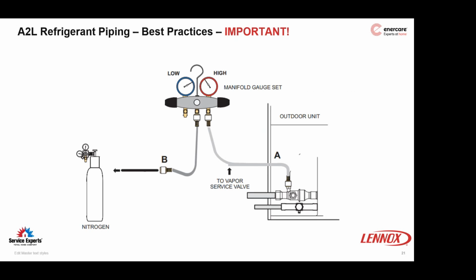Pressure tested. Leak test the system with our EnerCare operations manual minimum of 300 psi of nitrogen once all the connections have been completed and the Schrader cores have been reinstalled. That can be found in section 9. We're going to be following the same process as 410A refrigerant because the operating pressures of the new A2L refrigerants are pretty well the same.